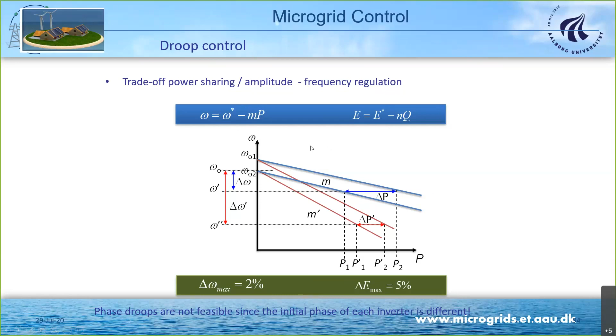In big power systems, the lines are basically inductive, so active power is coupled with angle and frequency, and reactive power is coupled with voltage. So what we do is the opposite effect: as the angle increases, active power increases, so we measure active power and then reduce the frequency, which reduces the angle. We do something similar with reactive power.